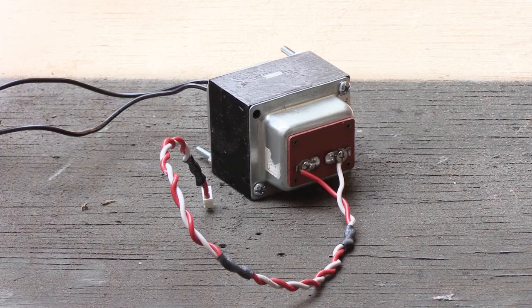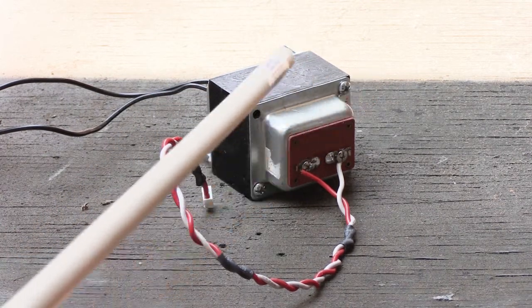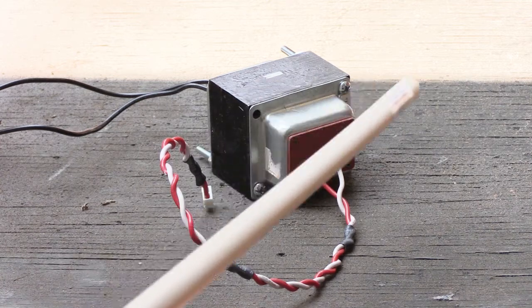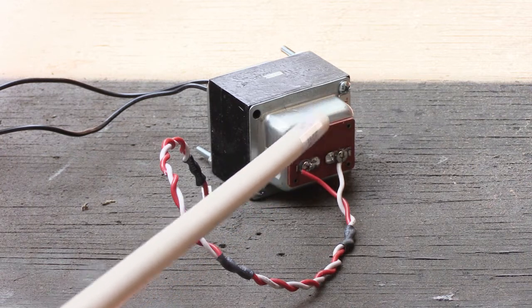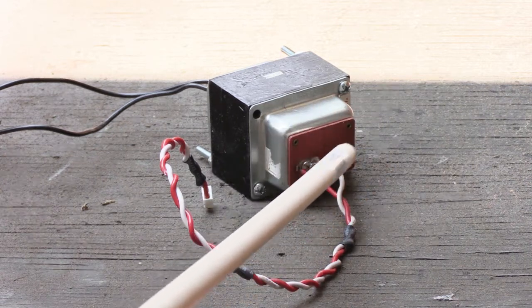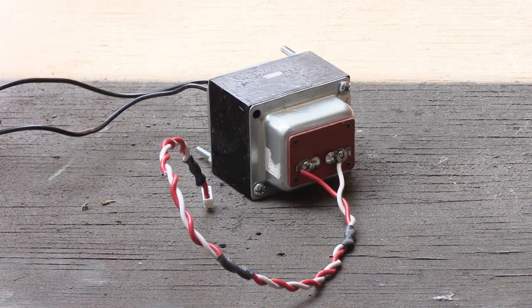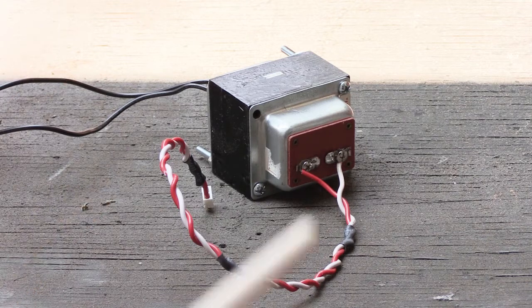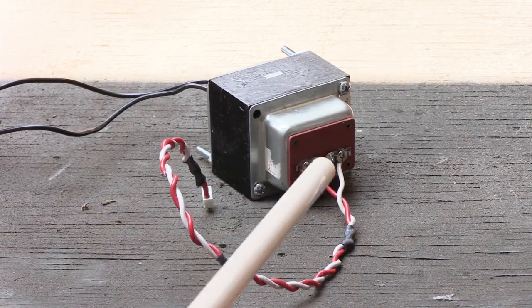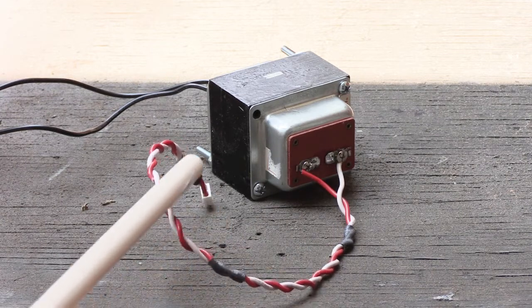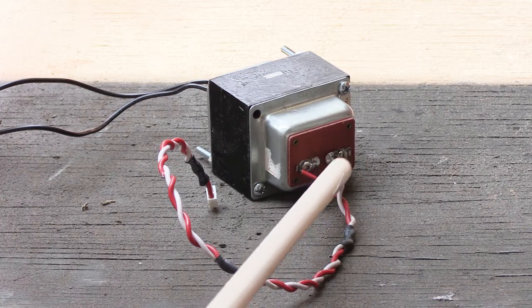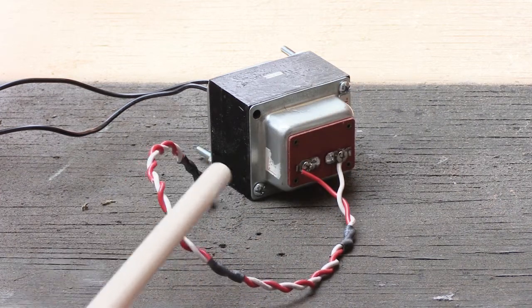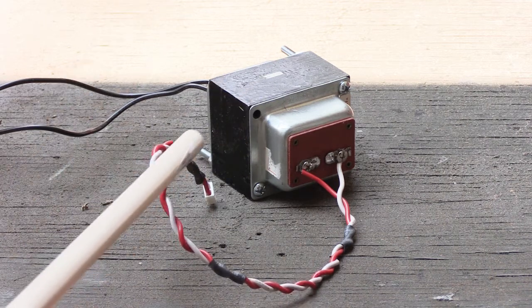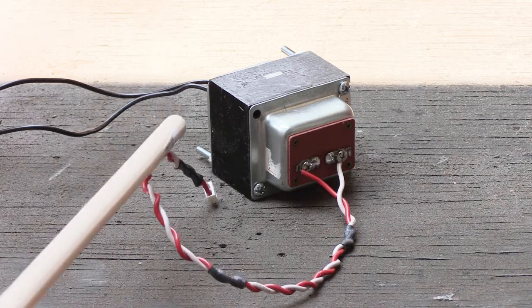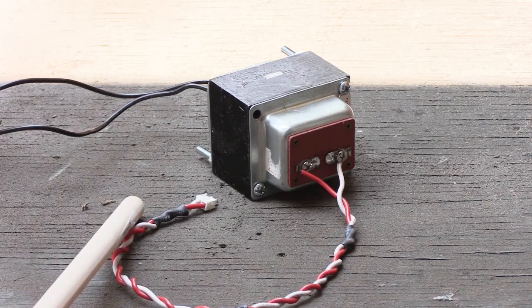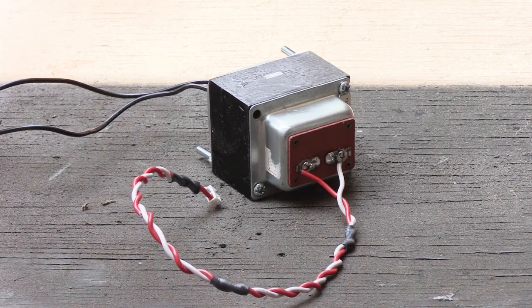Okay, it's time for our test. Here's what I've done: I took our 801T transformer, disassembled it like I showed earlier in this video, removed the fuse, and rerouted the outputs of the secondary, soldering them back onto the two screw terminals. To make this equivalent to what might happen inside the wall of your 4406 system, I used this red and white pair, screwed onto the transformer's terminals. This is an actual power lead cable from a 4406 power module. On the end with the little white connector, I took the pins that would go through the circuit board, bent them together, and soldered them. So basically what we have here is a dead short.